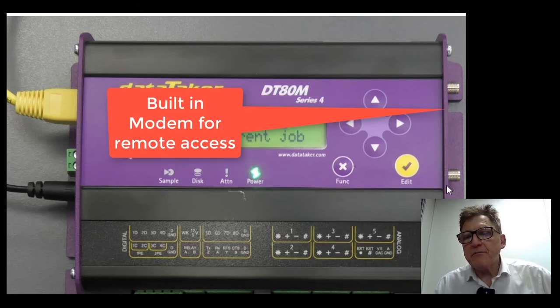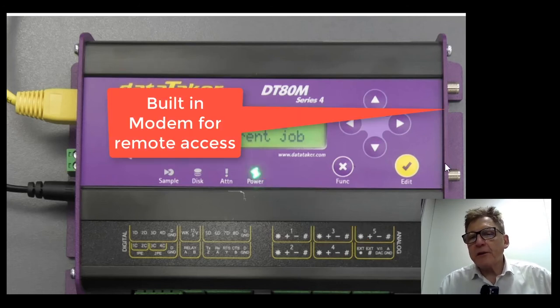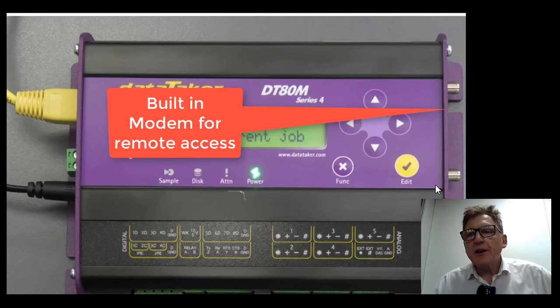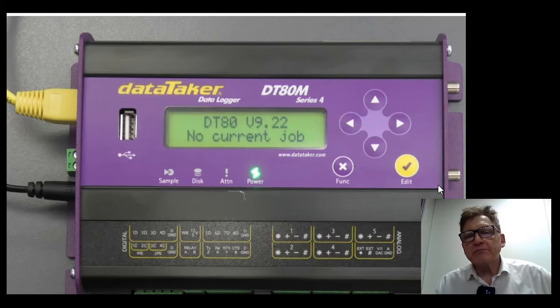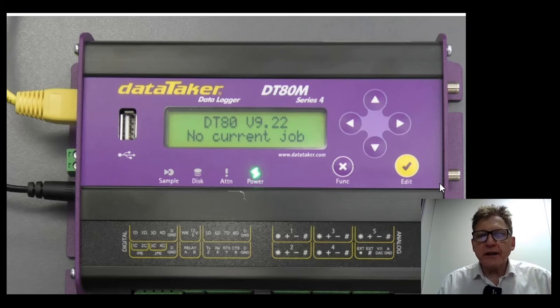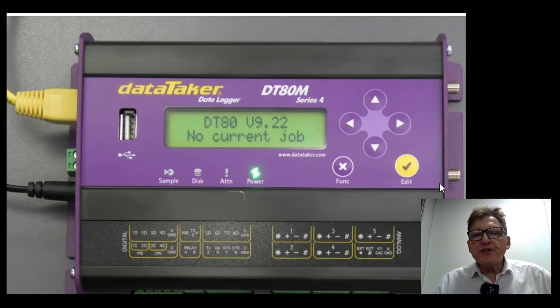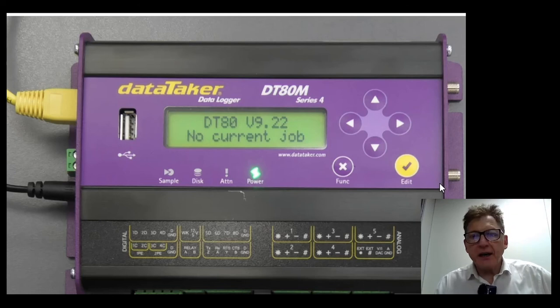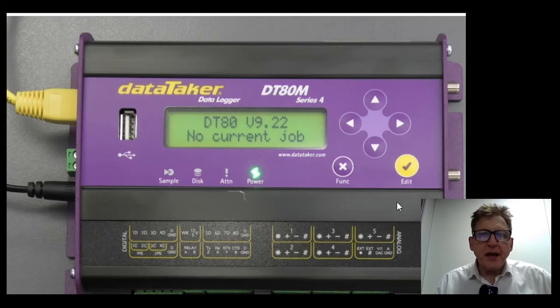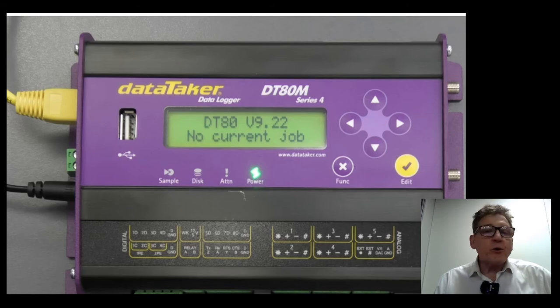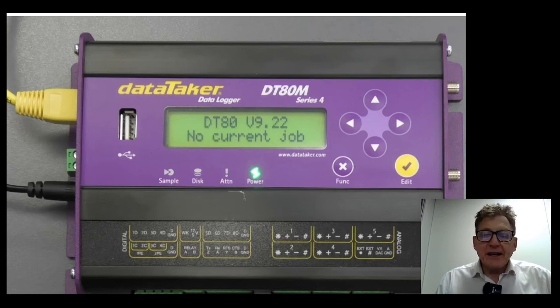It also has a built-in modem, so if you plug a standard SIM card in, you can email daily results or hourly results off. If you want to dial into the logger, you'll need a specially configured SIM card and you'll have to talk to us about that. So let's get on with talking about getting it connected.